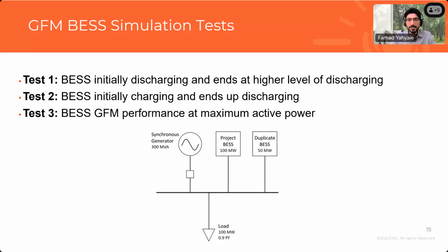The initial conditions of the three proposed tests are different. In the first case, both the project and the duplicate project are initially discharging, and after the synchronous machine trips, they discharge at a higher level. In test 2, they're both initially charging and then end up discharging after the tripping of the synchronous machine. In test 3, one of them is at maximum power, so once the synchronous machine trips, we expect the output of that unit not to change, while the other unit picks up the load.